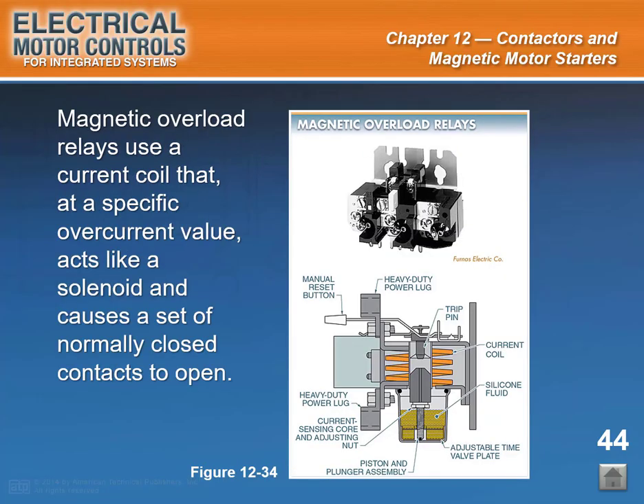Start of slide 44. Slide caption: Magnetic overload relays use a current coil that, at a specific overcurrent value, acts like a solenoid and causes a set of normally closed contacts to open to shut power off to the motor. See Figure 12-34. Magnetic overload relays provide another means of monitoring the amount of current drawn by a motor. A magnetic overload relay operates through using a current coil. At a specified overcurrent value, the current coil acts as a solenoid, causing a set of normally closed contacts to open. This causes the circuit to disconnect the motor power to protect it from damage. End of slide 44.